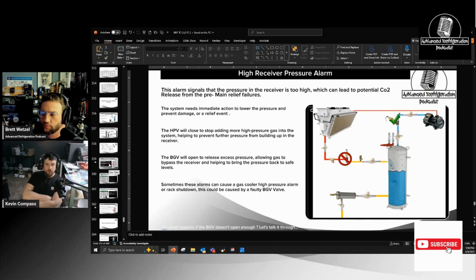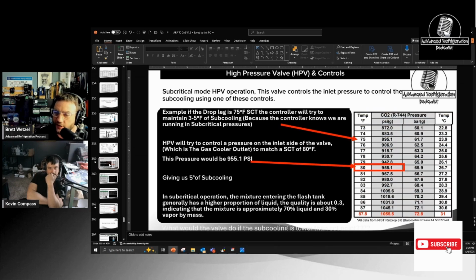So if you see them hunting all over the place, open, close, slamming all over the place, it may be low on gas, especially if it doesn't have a liquid level in the tank. Yeah, it's the only time. This was a weird concept for me to wrap my head around until I really thought about it like you just did. I was trying to explain this to someone the other day, and I was like, this is the only time where low refrigerant level will essentially cause a high pressure issue. And then that's what I basically explained.